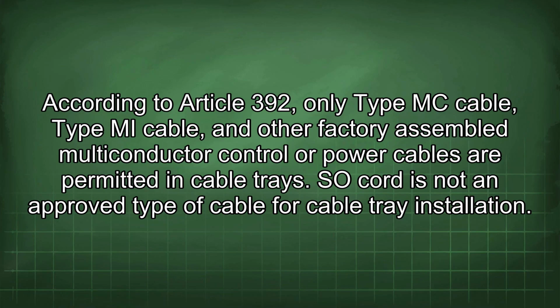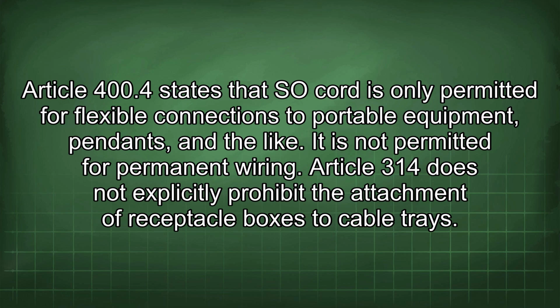According to Article 392, only Type MC cable, Type MI cable, and other factory-assembled multi-conductor control or power cables are permitted in cable trays. SO cord is not an approved type of cable for cable tray installation. Article 400.4 states that SO cord is only permitted for flexible connections to portable equipment, pendants, and the like. It is not permitted for permanent wiring.